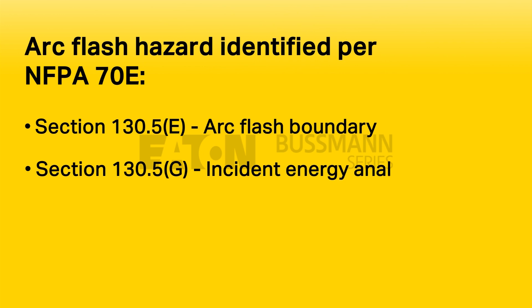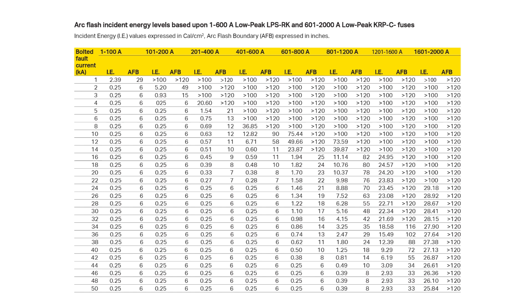The first step is to determine the available fault current on the line side terminals of the equipment that will be exposed. Second is to identify the upstream low-peak fuse that is protecting that equipment. A table as shown here can then be used to identify the incident energy level exposure expressed in calories per centimeter squared, and the arc flash boundary that will require personal protective equipment based on this energy level.